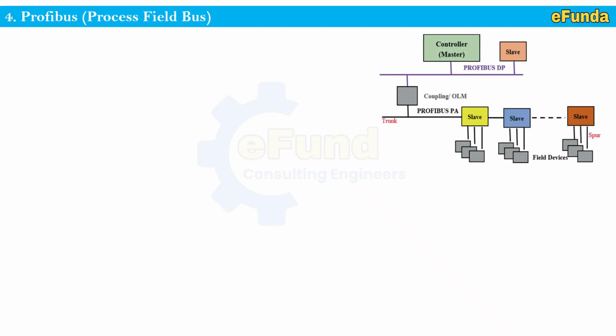Fourth, Profibus, that is Process Field Bus. One can refer to the picture where the typical architecture of a Profibus network is shown, starting from the field devices where the slave connections are shown and the spurs are shown as well. Then similarly the trunk is shown for connecting the controller, that is the master, to the slave.